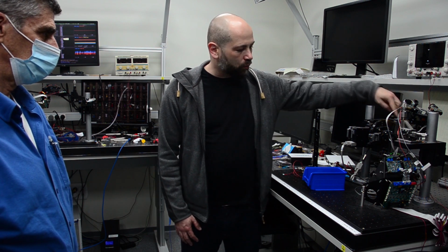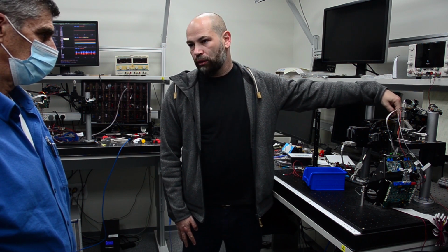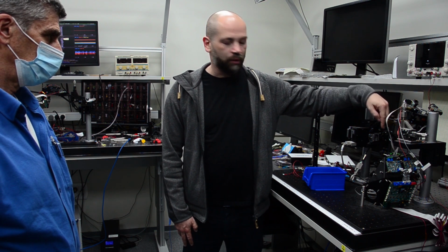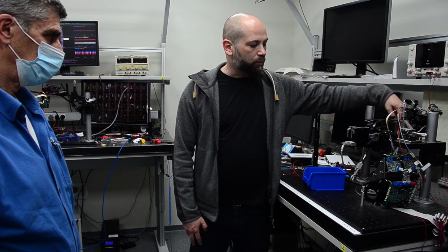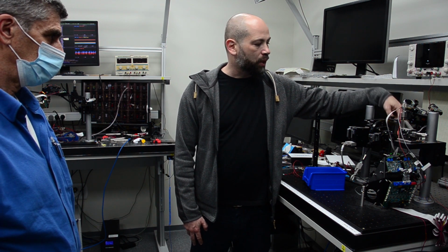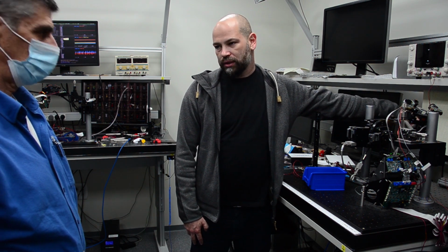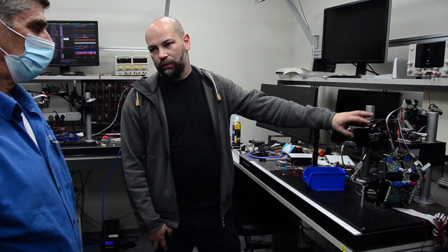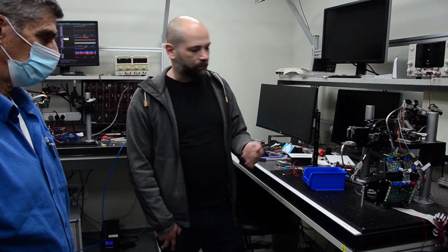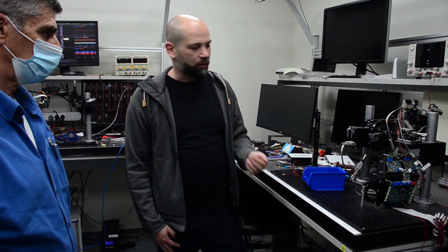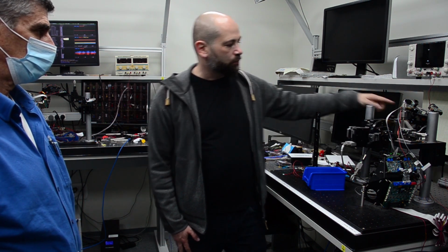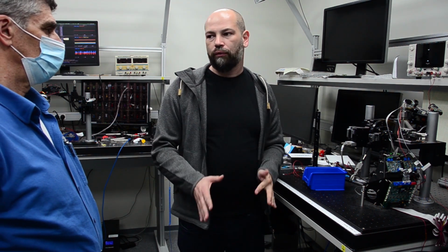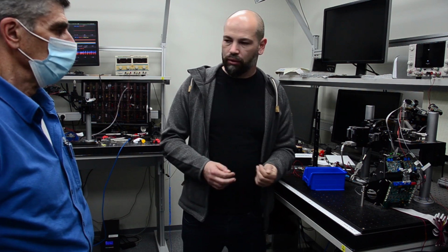Now, what you see here, since there is a see-through system and you can see the world, you can see the green laser entering the eye, reflected back through the optical system, and part of it is escaping and hitting this page. So if we move the eye right now in a non-tracked mode, as Faris will present it to you right now, you will see that the beam will not move here. That means that the eye is a very good reflector. It doesn't distort the angle of the beam.